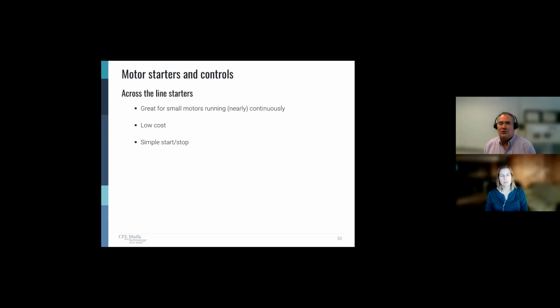So we got a couple of options here for starting motors. There's the time-honored method of just starting them across the line. Most small motors are started this way. You flip a switch and the exhaust fan starts. They're low cost because there's really no cost, and they're simple start stop. Small fractional horsepower motors, they put a capacitor on the side of the motor, which helps that, and you're off to the races. We don't want a motor that starts and stops a lot because it's going to be stressful. But for a motor like a fan where we start it and it runs, we don't worry about it. Not a problem.